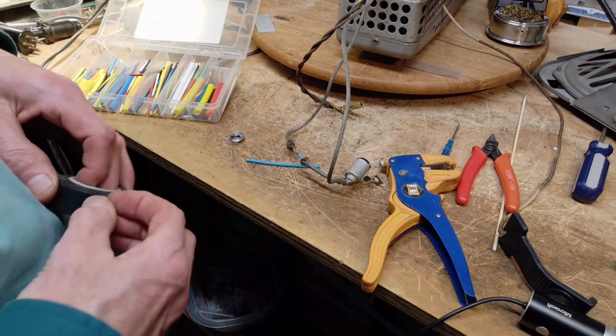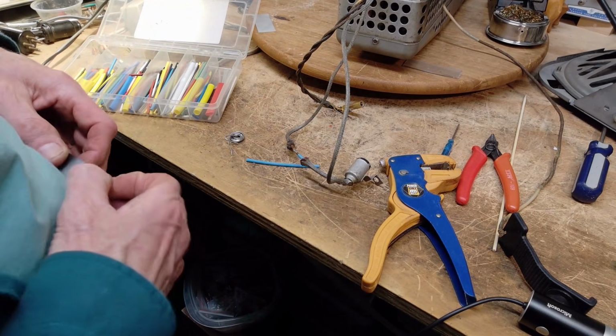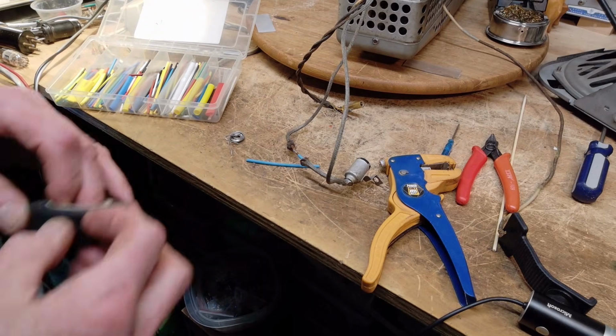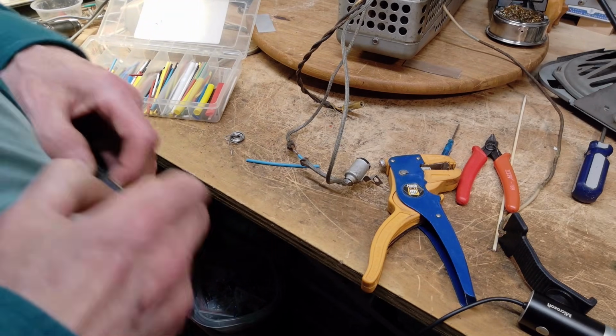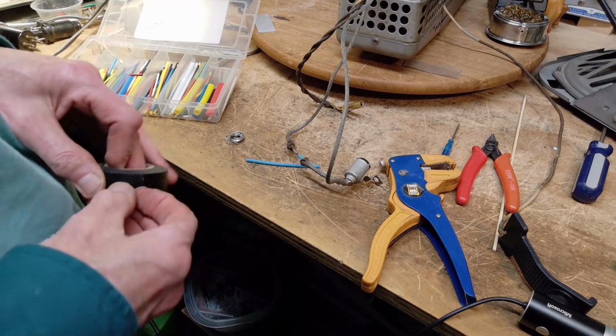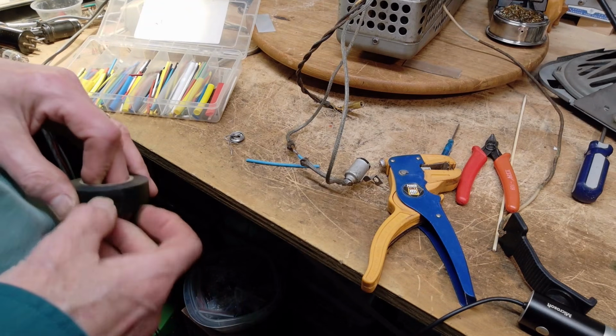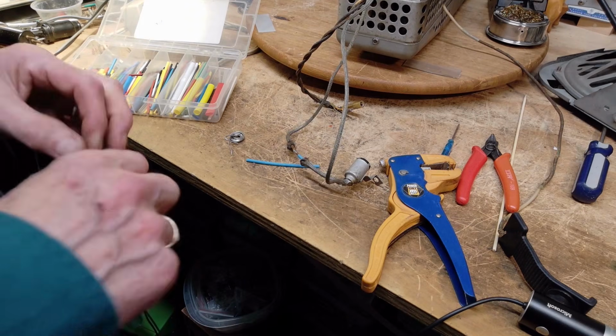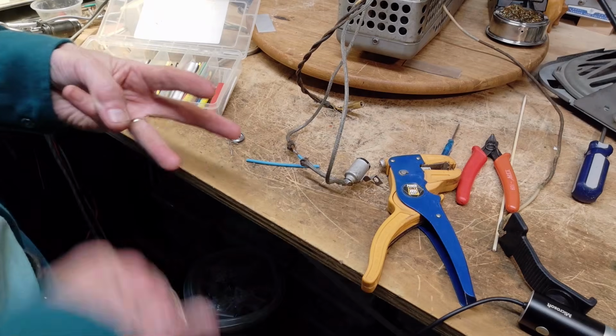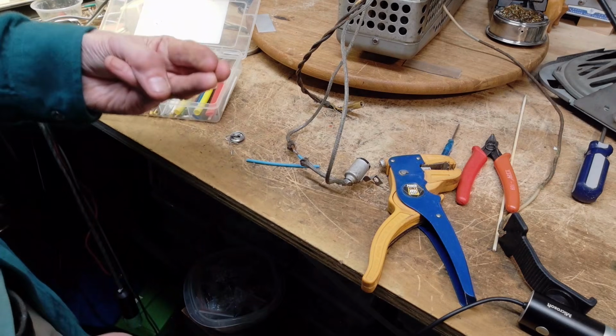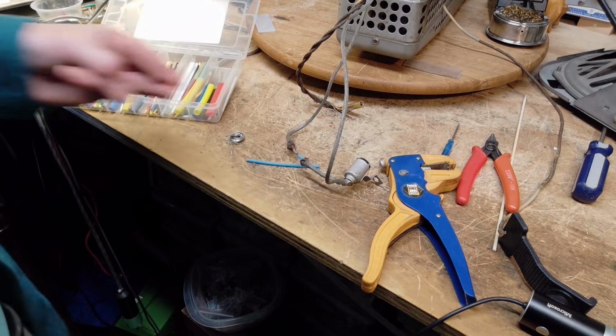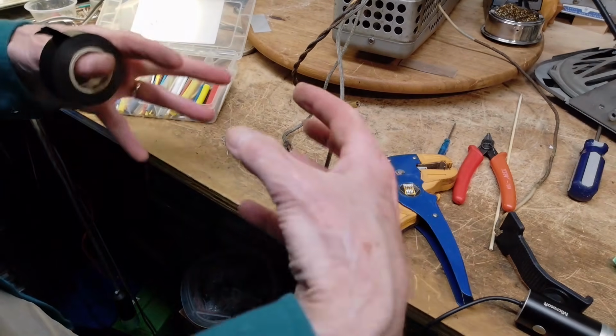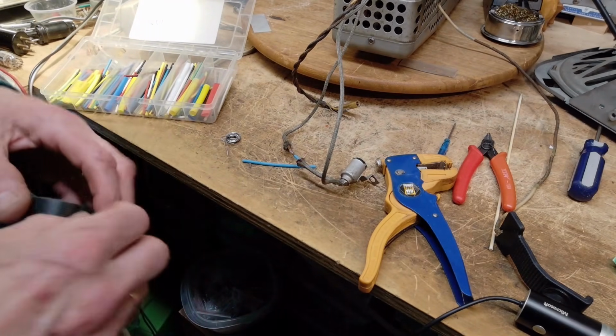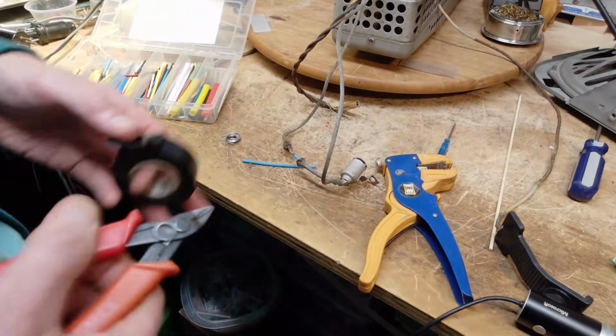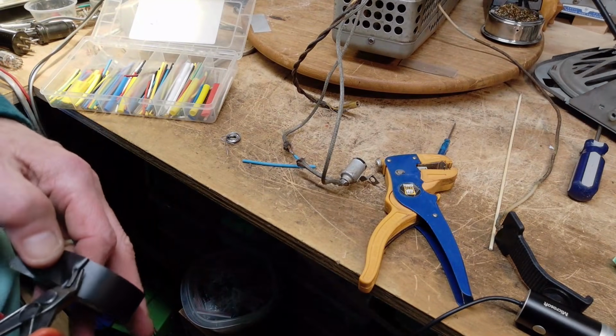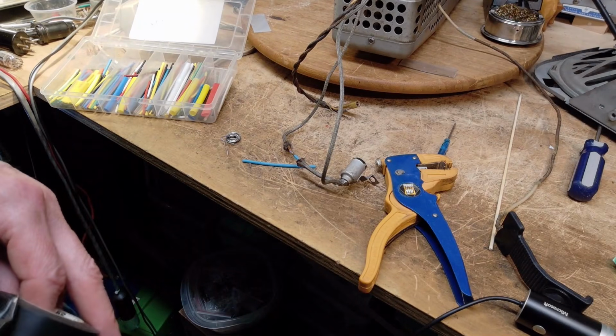Many of the failures in an electric system can be in the splices made between these big cables, and if you think doing something like this is involved, it's not. Splicing these great big cables together is very involved, and it does require a lot of skill to do it. It's an all-day process to make one splice on a three-phase cable, and these conductors would be more like that - each conductor about that size. Three of these guys this way, and three come in this way, and you've got to get them together, and you've got to sleeve them. It's really quite a trade, and it takes a long time to build up enough experience.